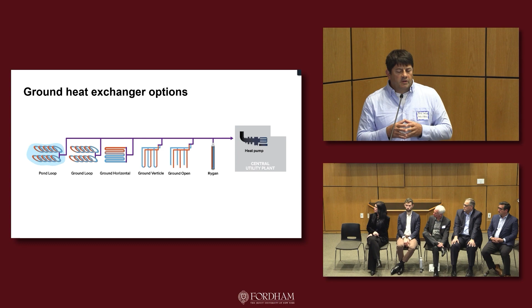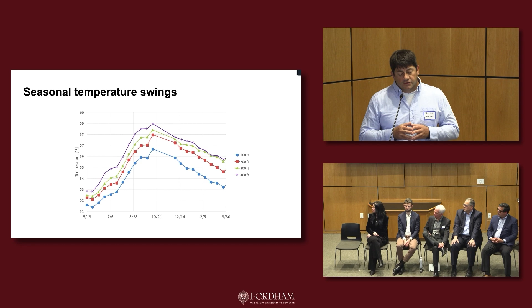Kind of back to what I was talking about with fiber optics—this is a project we did 12 years ago, our first fiber optic project, where we actually measure the ground temperature every 50 feet. You can see the traditional sine wave of the ground heat exchanger, and how this project actually shows a temperature change. Sometimes we see ground heat exchangers so oversized they don't change temperature at all. So what happened there? Your client just paid way too much money for a ground heat exchanger they're not utilizing—it's just sitting there. But it's giving your heat pumps optimal water temperatures to operate in. It's all about that first cost scenario.